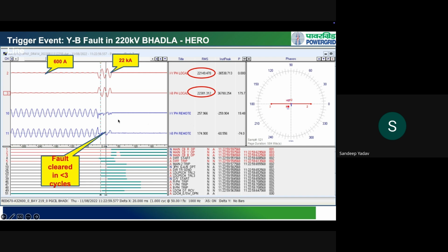However, the differential relays work on the principle of difference of current between the grid side and the inverter side. The difference would be 22 kiloamps minus 257 ampere. So there will be a large differential current, which will be seen by the differential protection, and it will work just fine. You see at this digital input, as soon as it detected the fault, it issued the differential trip and opened all 3 circuit breakers. So the idea was to show you the fault contribution from the grid side and from the solar plant side.